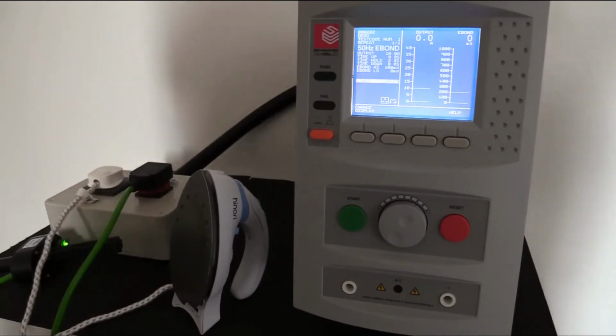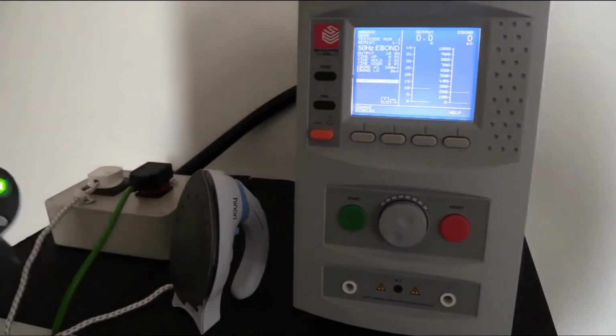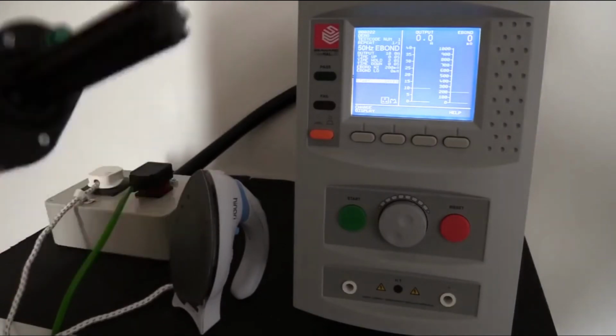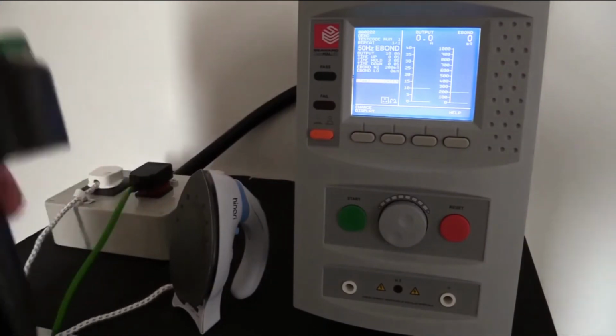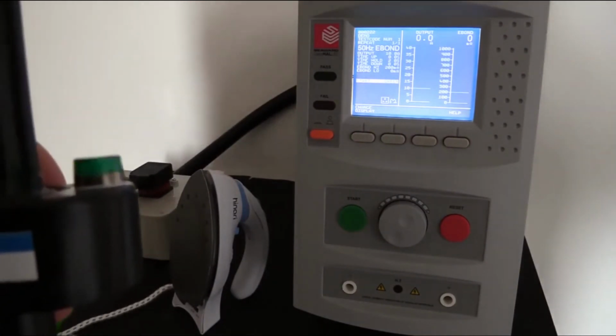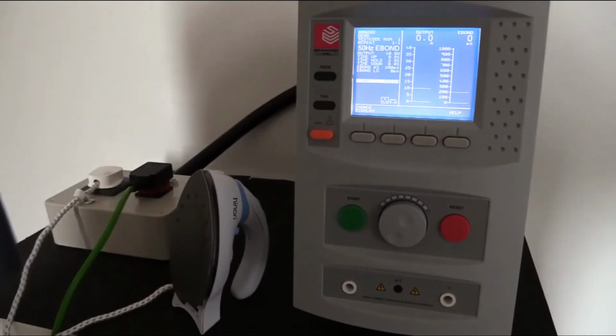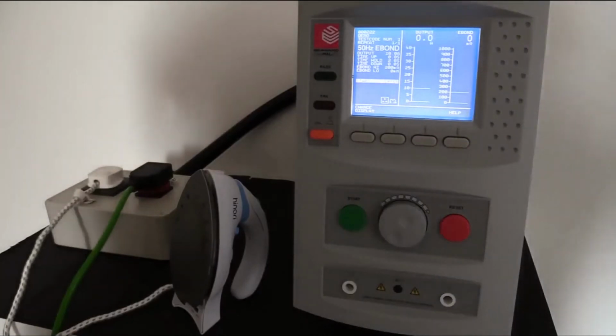So the probe is used to give feedback to the operators when it's needed for the test. You'll notice right now it's flashing very rapidly. So that's the indication to the user that this probe is required for the test. Now during the test the probe will continue to flash, but it will slow down to show that the test is in progress. Once complete, the probe will also then give indication to the operator as to whether the test passed or failed. It does this by, if the test has passed, the light on the probe will stay green. If it fails, the light will go out, and we'll also get visual indications on screen.